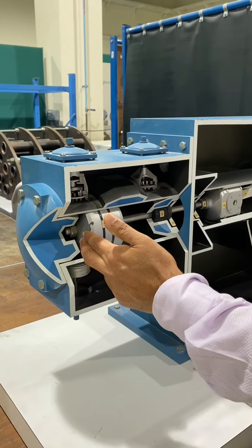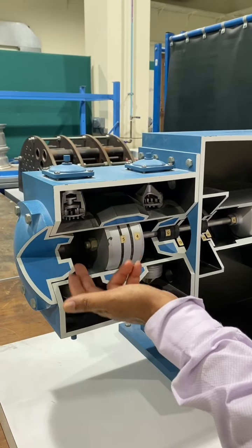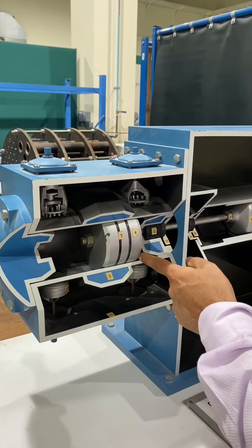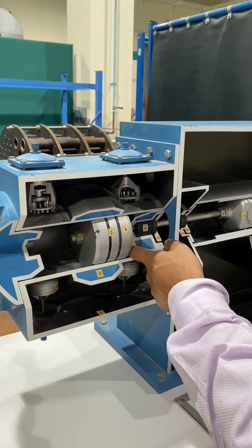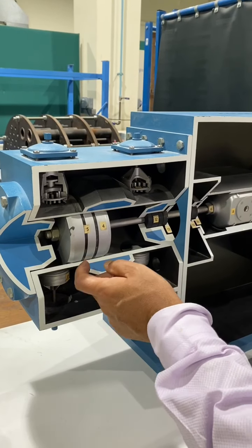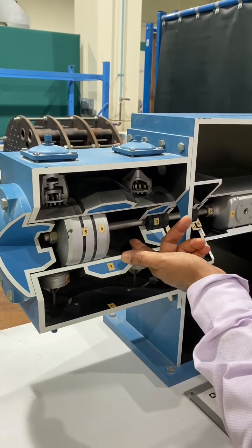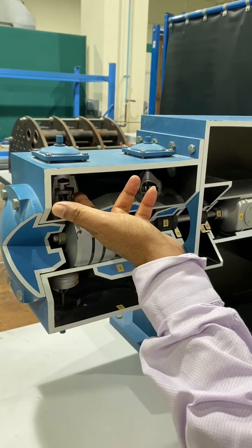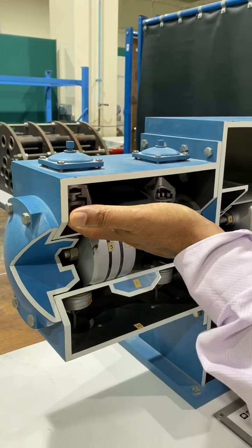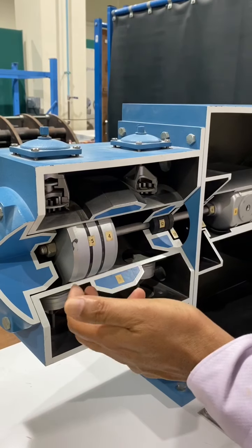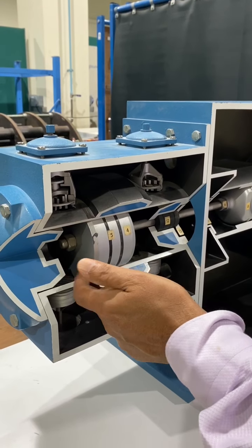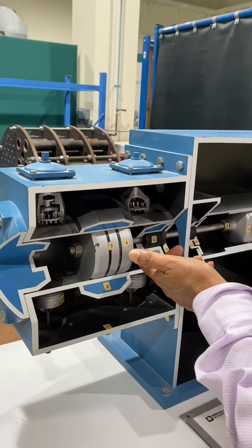So see, when this is rotating, the suction comes here, the gas or air is coming here, and after some time the compression takes place on this side also. You can see this is going in, and the gas is coming from here and pushing the piston this side, and this gas will be compressed here. When it is compressed, the compressed gas or air goes out from this side. Same thing here also: suction here, and at the same time compression takes place on the other side of the piston. Then when it is compressed, the gas escapes through this. That's why I called it double acting.